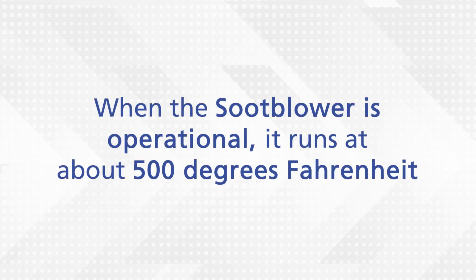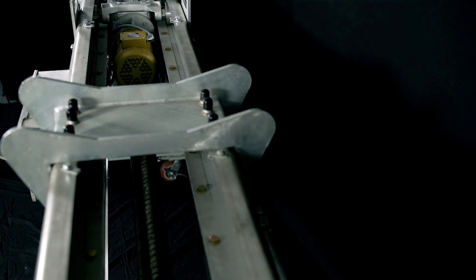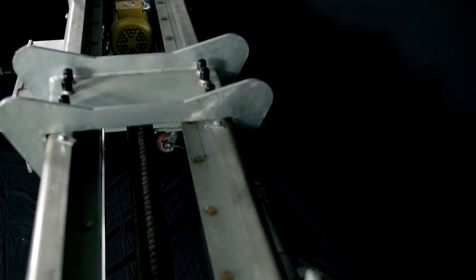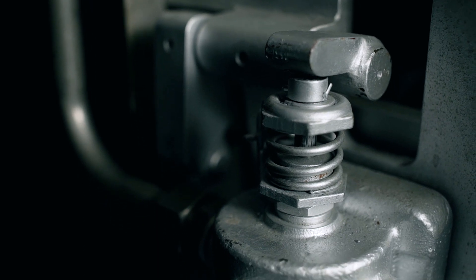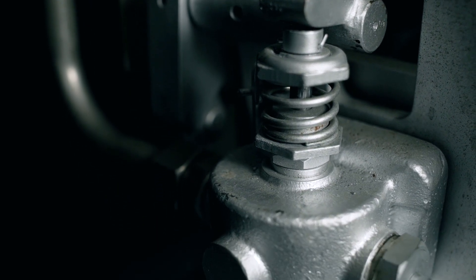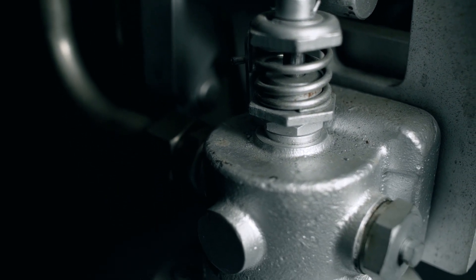When the soot blower is operational, it runs at about 500 degrees. But when the soot blower hasn't been running for a long time and the feed tube reaches temperatures over 200 degrees, there is a possibility of an internal steam leak in the poppet valve.